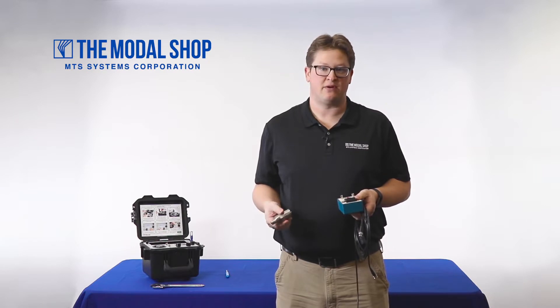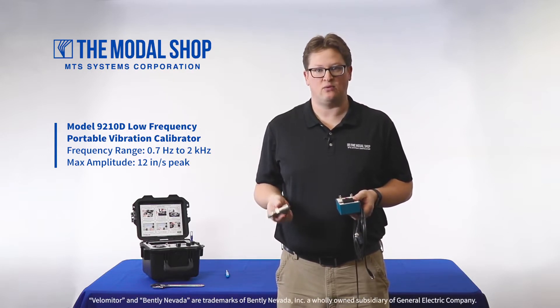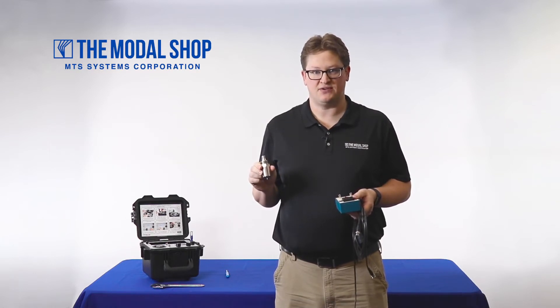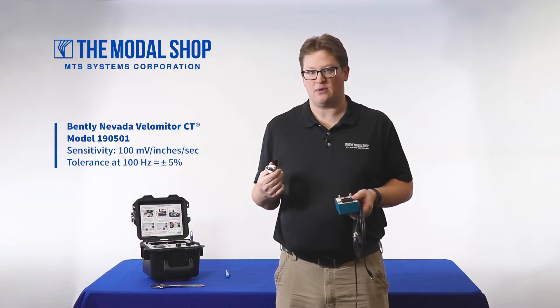In today's video, I'm going to use our Model 9210 Low Frequency Portable Vibration Calibrator to perform a frequency sweep calibration on the Bently Nevada Model 190501 Velomitor CT Vibration Transducer. This sensor is 100 mV per inch per second with a plus or minus 5% tolerance at 100 Hz.